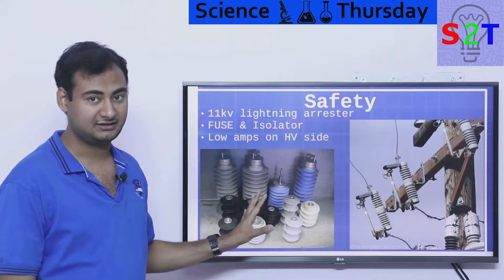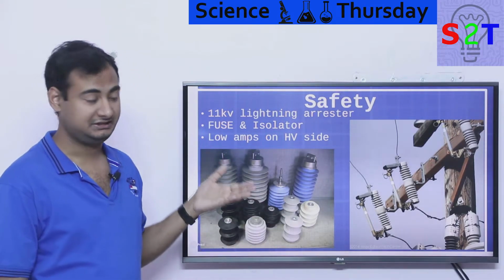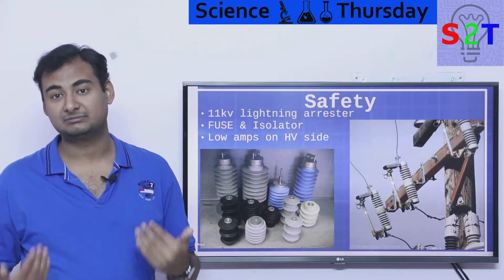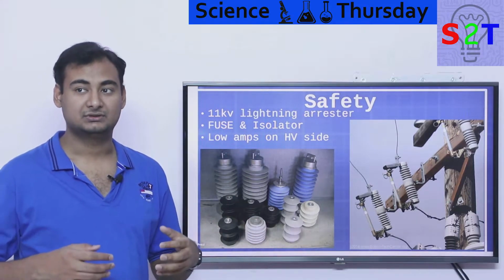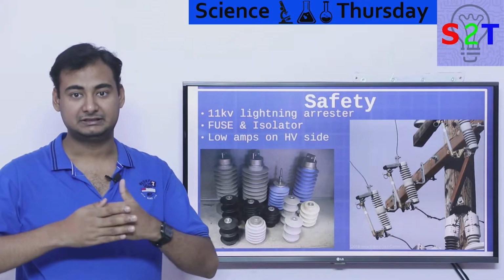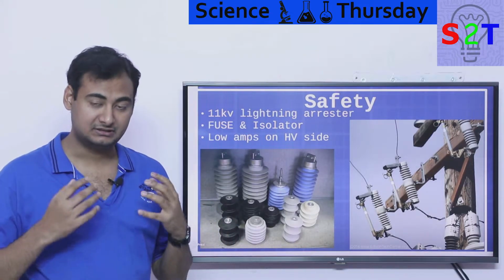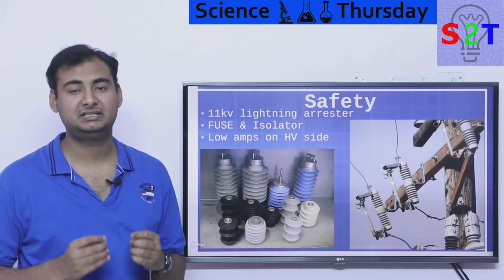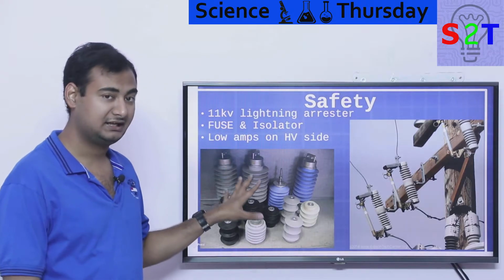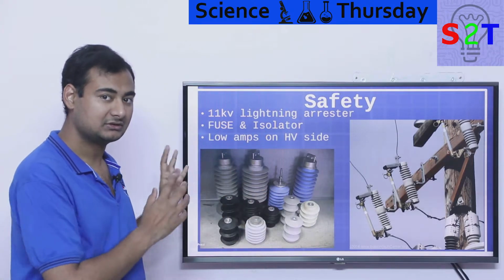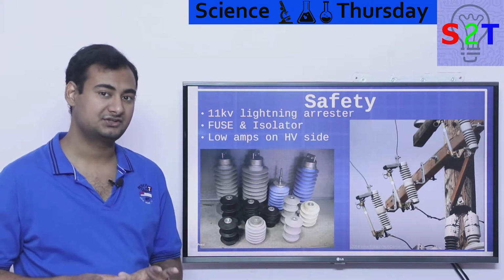This is the first line of defense. However, you should understand that even though these are lightning arrestors, they also sometimes act as surge arrestors. So let's say in a substation a fault occurs and they're opening the switch or closing the circuit breakers; sometimes this also releases a very high voltage spike. This acts as double duty, basically serving as a makeshift surge arrestor too.